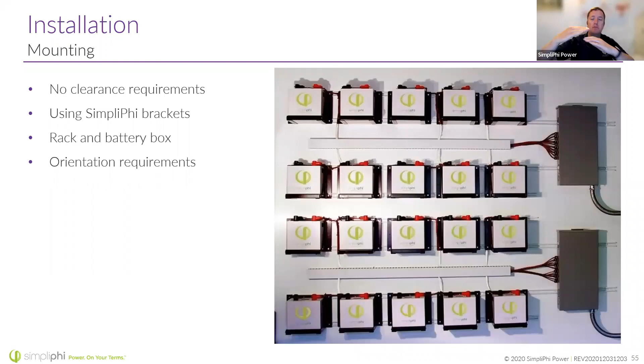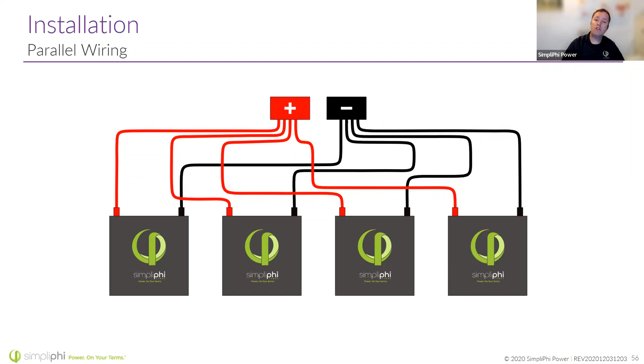When it comes to wiring these batteries, it's a bit different from the old lead acid battery days. We're always going to do parallel wiring, but instead of going positive to positive to positive and then a home run to the equipment, we don't want that. What we want is conductors of the same length and gauge going to a common terminal connection point, then feeding into a much thicker conductor up to the equipment. This prevents batteries from working harder than others and avoids voltage drops in the lines.